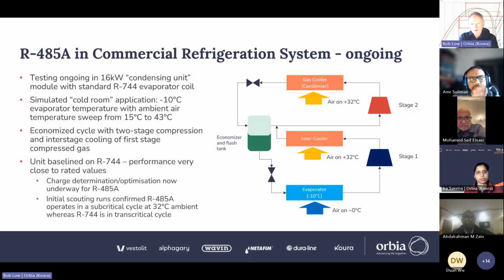We finished a baseline on the unit with CO2 and we basically tested all of the medium temperature rating points from the European standard. And the measured performance, happy to say, is very close to the catalogue data. It's actually slightly better, but you'd expect it to be slightly better. We've got enough information to back out the compressor performance map, for example. And where we are now is we're doing charge determination for 485A. We had one run at it, but we got the charge determination wrong and flooded the economizer. So we're going again with less charge and hoping to have results in the next couple of weeks.